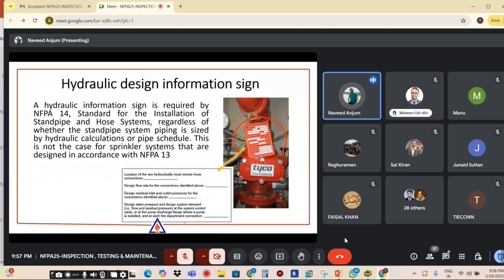Then hydraulic design information must be present in our standpipe system as per NFPA 14. We have to check during our inspection that there is a hydraulic design information sign on our standpipe system.